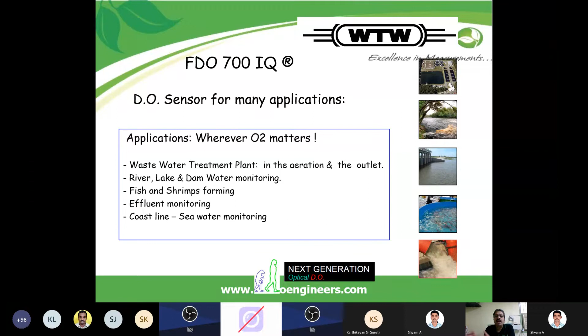The DO sensor is used in many applications, as I said: wastewater treatment plants and the aeration tank outlet, but also river, lake, dam and water monitoring, fish farming, effluent monitoring, coastline and seawater monitoring. So we have lots of applications for dissolved oxygen. Measuring the dissolved oxygen in a process will help to reduce power by controlling the motor. Once it achieves a particular oxygen level, this motor, which is running 24 into 7, can be stopped or slowed down.